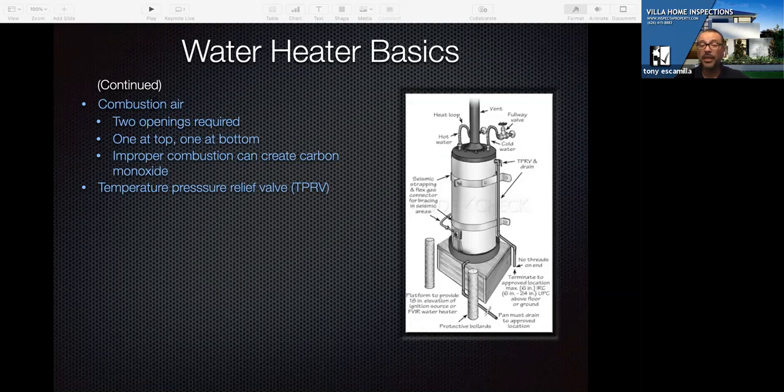I had one recently where the tenant was being asked to relocate because the seller sold the property. Tenant was not happy about it. What did they do? They went to the little control knob for the water heater as they were leaving, turned it all the way up. And when we got there about 2 or 3 days later to do the inspection, we were wondering why there was flowing water out in the backyard and why it was steaming.